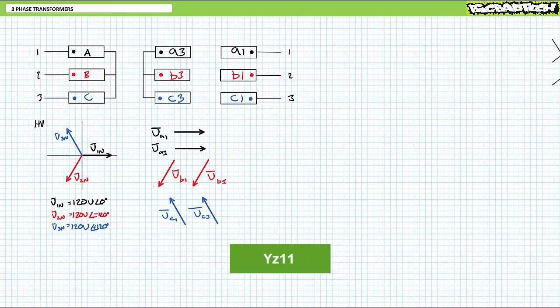A properly configured YZ11 connection ties together the dotted ends of A3, B3, and C3. Not the non-dotted ends, the dotted ends. And then rather than sticking with the respective phases, the non-dotted end of B3 is joined to the non-dotted end of A1. The non-dotted end of C3 is joined to the non-dotted end of B1. And finally, the non-dotted end of A3 is joined to the non-dotted end of C1.